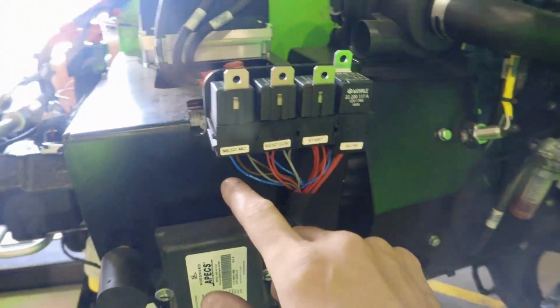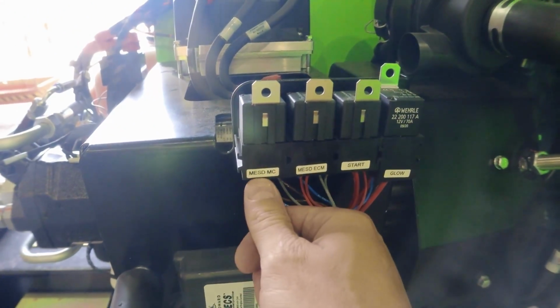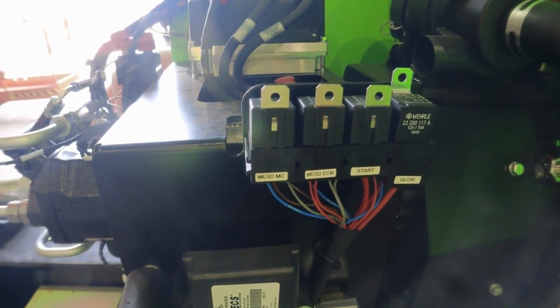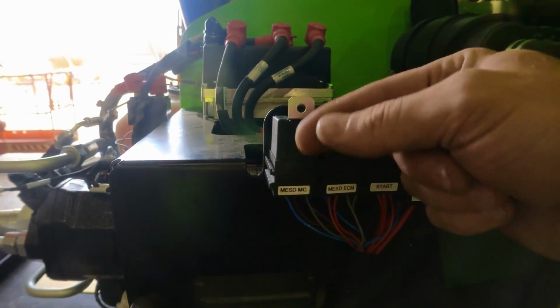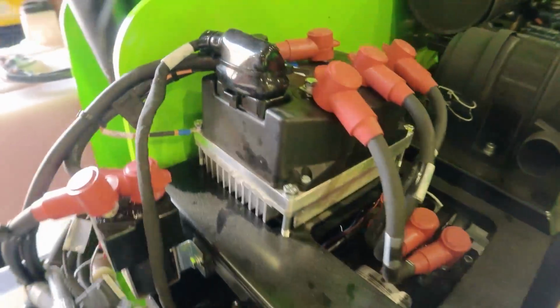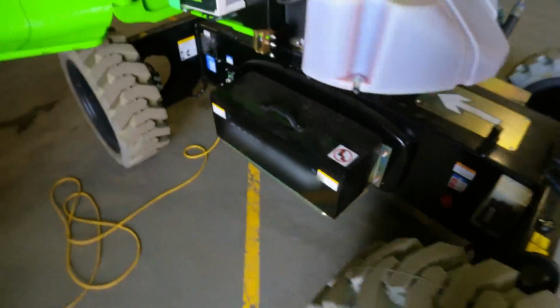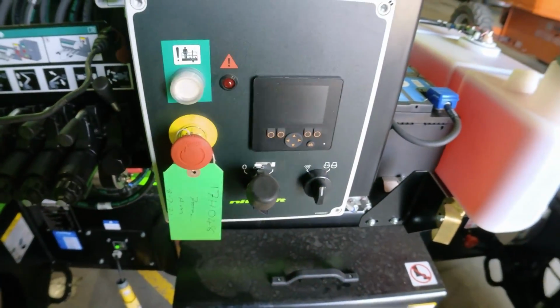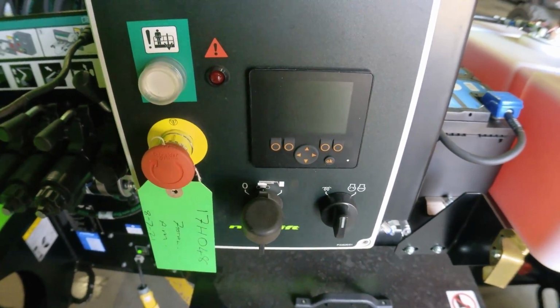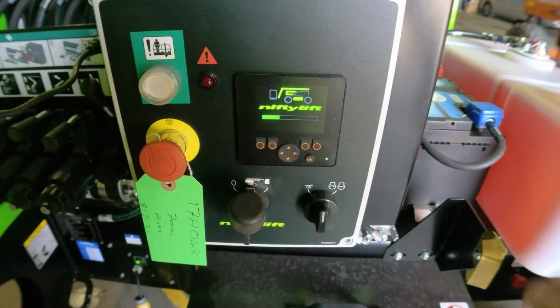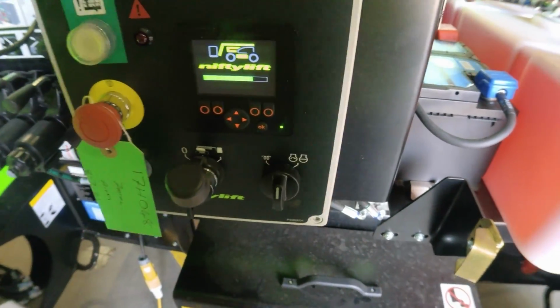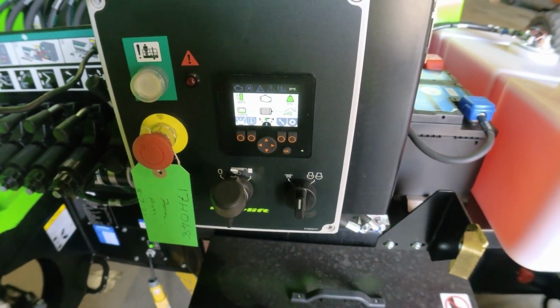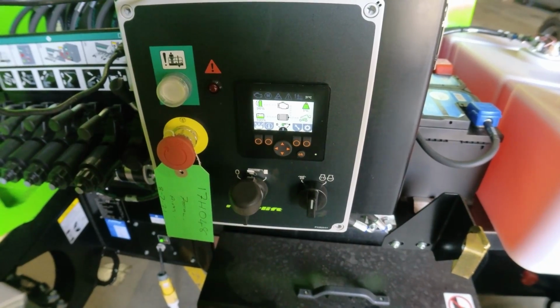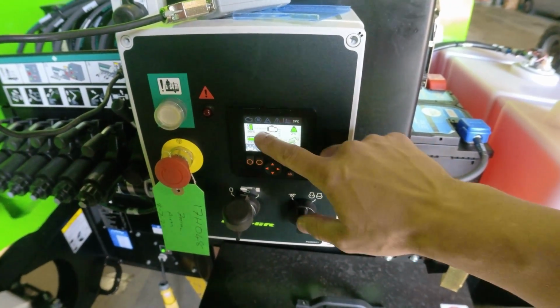Is this the relay here? Okay, that's the motor controller enable relay, and I moved the relay in and out, and the motor controller has tripped out. So if I restart the machine, I think I will get the motor controller back on. Let's try. Yeah. So I restart the machine, and the errors have gone.